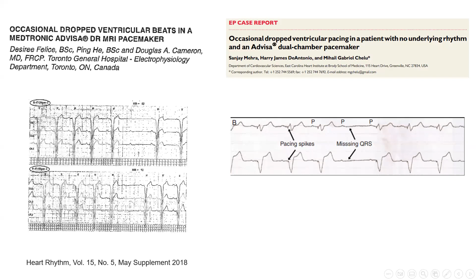This is a non-programmable feature in the Advisa MRI pacemakers. This feature occurs every 1 hour, and it takes time for the feature to act, so there is an additional 30 seconds each time it happens. What's happening every 1 hour, in those 30 seconds, is that there's a collection of the EGM for reference. It's available on the remote system, and as the pacemaker collects the EGM, there is an amplifier for the EGM. The turning on and off of this amplifier can cause residual noise that can inhibit the V-pace.